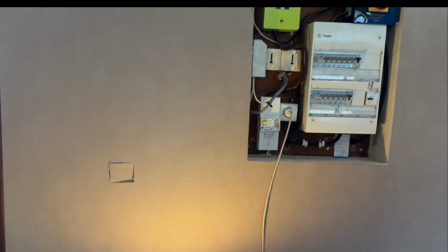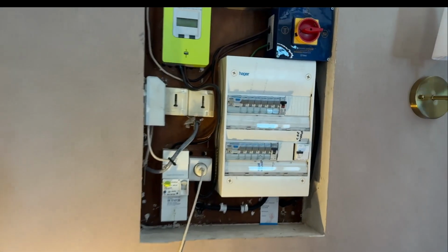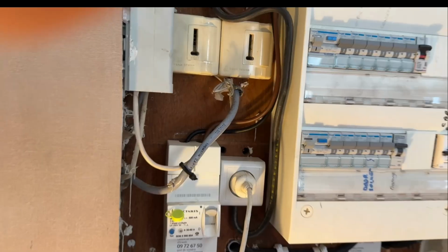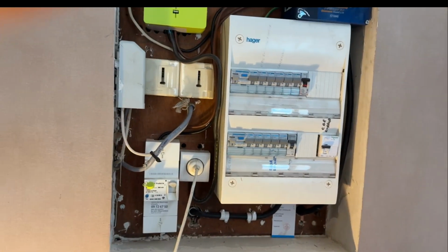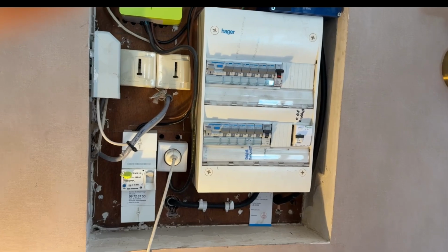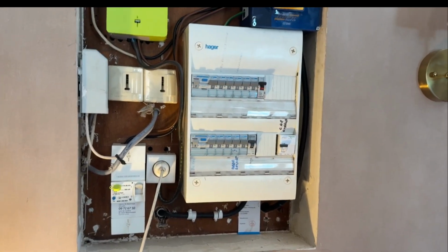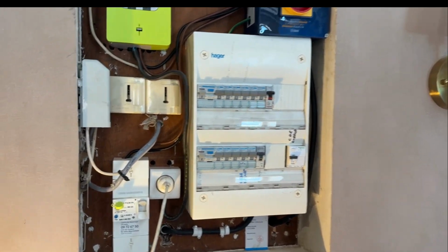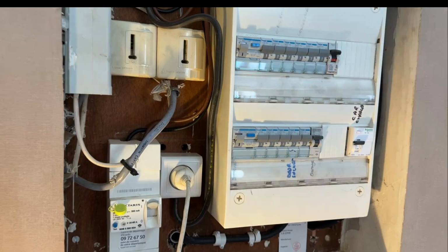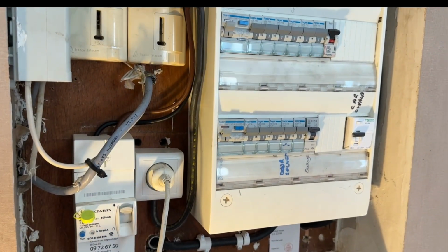The main breaker board for the house is in the bar. It's here behind this painting that's usually on the wall. There are some features that we've added here. So this socket here is connected only to the mains power coming into the house. It's not connected to the rest of the house circuit. So if you're running on the generator and there is no mains power, then there's no power to this socket.